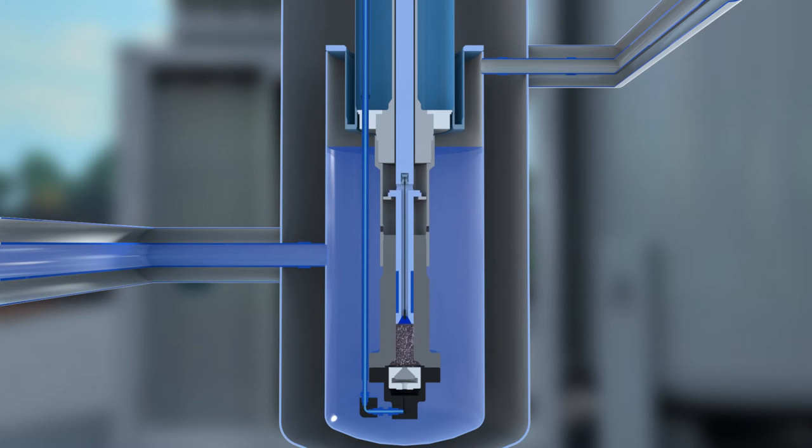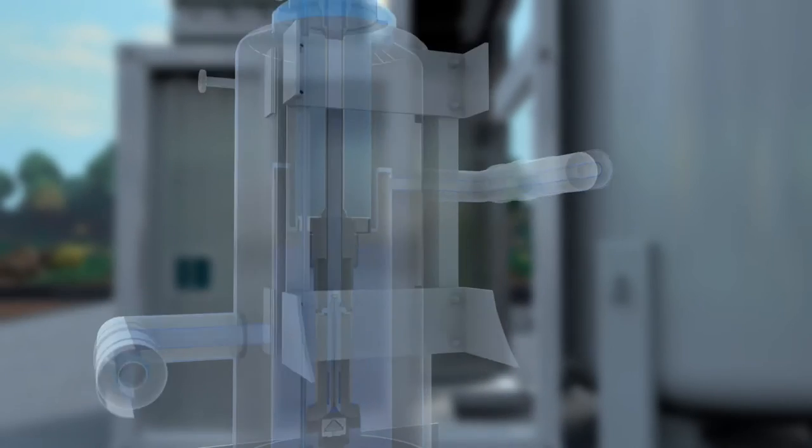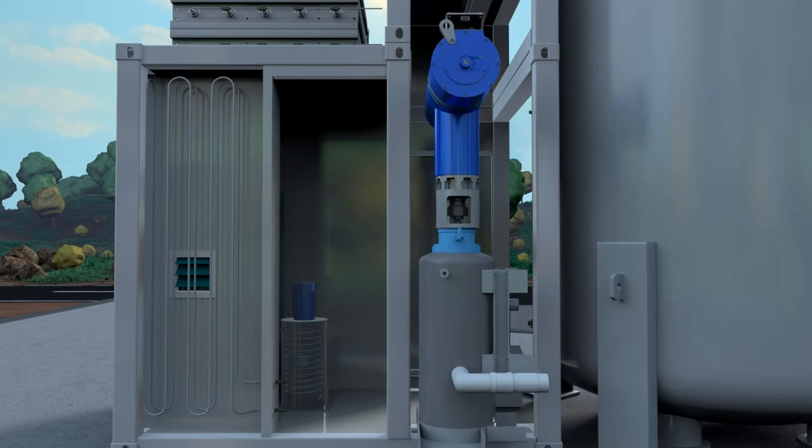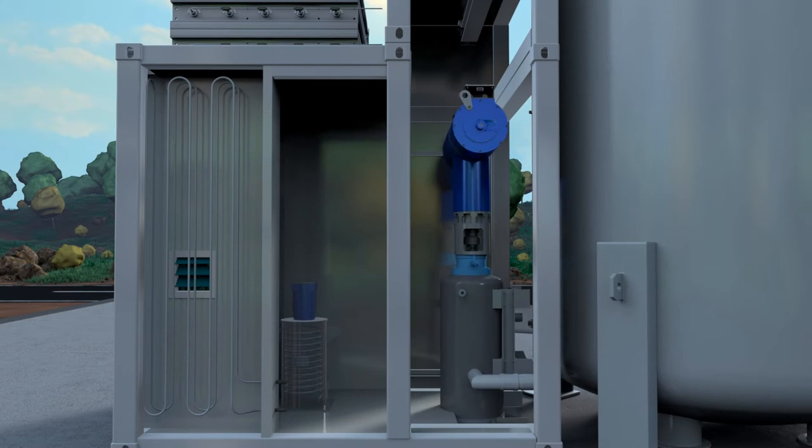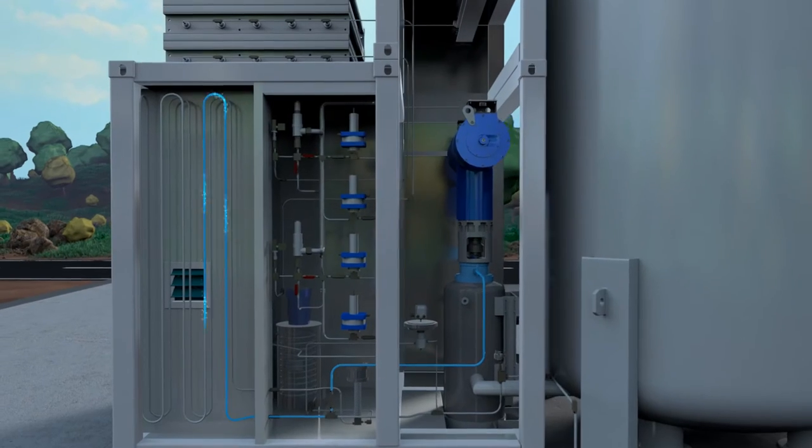The downward movement of the piston then compresses the hydrogen in the second chamber to a final pressure of 900 bar. The hydrogen is now gaseous. Due to the direct compression of liquid hydrogen, the Cryo Pump consumes only a fraction of the energy required by a conventional compressor.